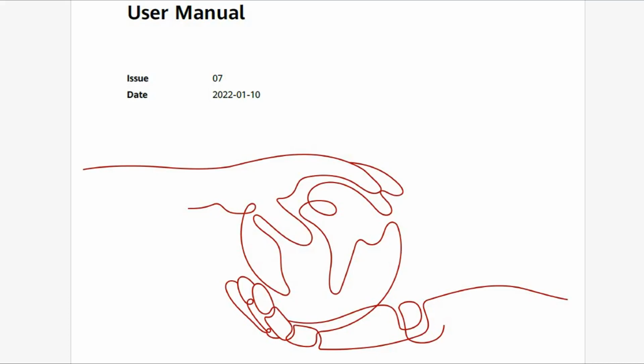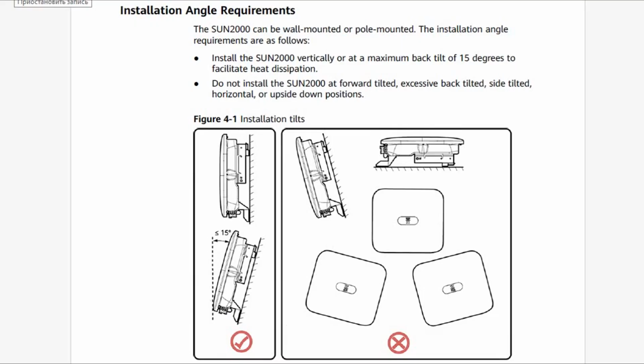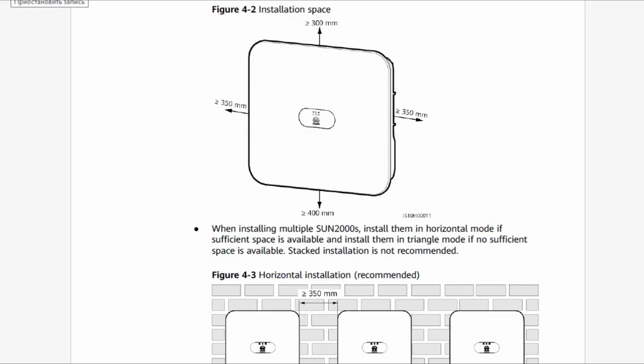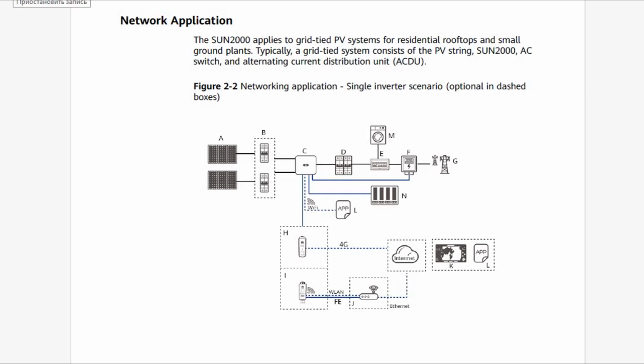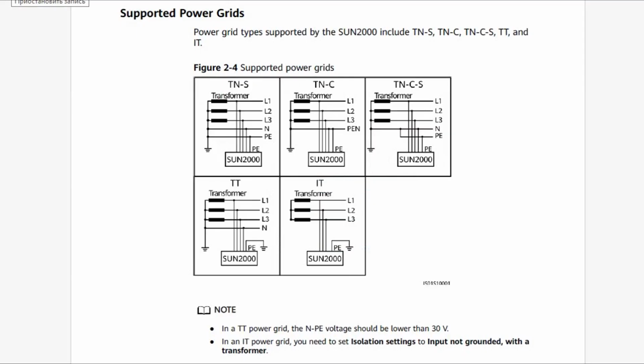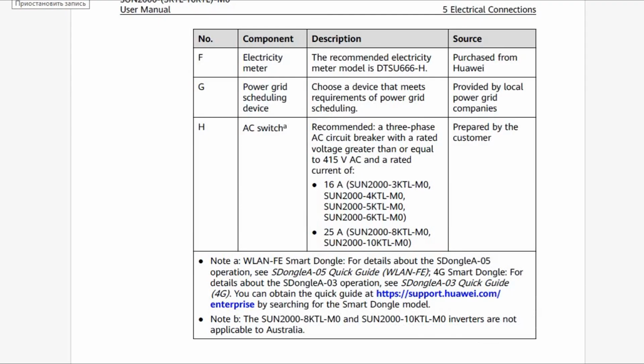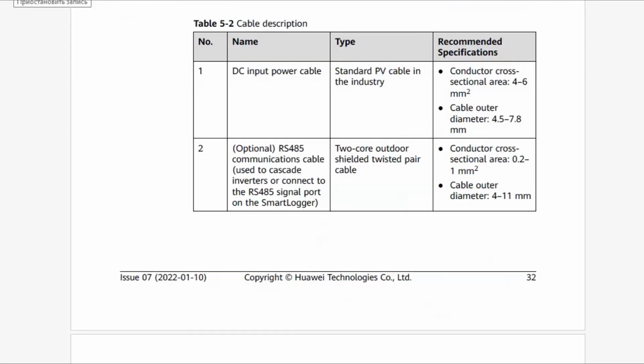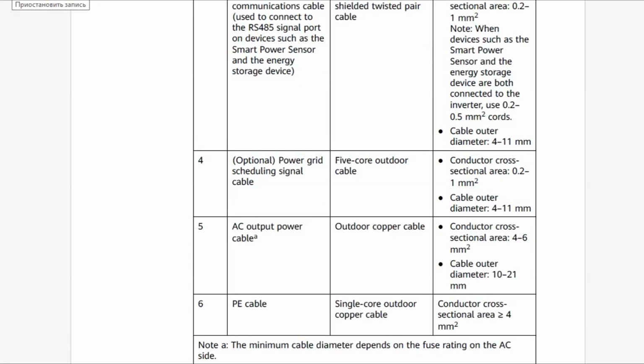Before installing any electrical equipment, we carefully read the corresponding installation manual. The correct functioning and reliability of the equipment directly depend on following the manufacturer's guidelines. Moreover, if the installation requirements are not met, the manufacturer has the right to refuse warranty service. The manual contains a lot of useful information: installation data, wiring diagrams, required cable cross-sections, characteristics of protective devices, and much more. We use this information when purchasing materials.